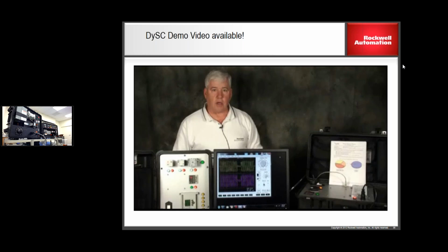It also happens to be more than a second, so we can see the numbers count. I'll ask you to notice the timer up here. All I'm going to do is reset this, and now I'm going to put in series with this load the DySC. So now I'm going to put protection in front of it using this dynamic sag corrector. I'm going to create the same event we just did that lasted just over a second that affected this line. I'll warn you, it might be kind of boring, except for those numbers changing, but let's start that sag. Kind of boring.